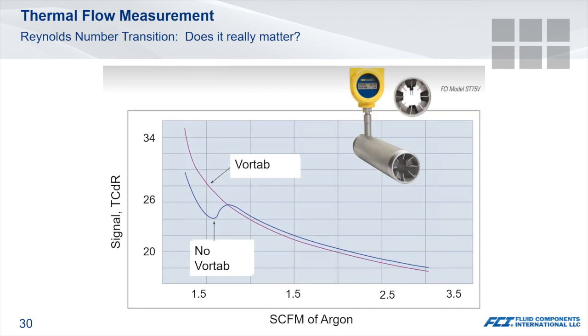This next illustration helps visualize how transitional flow can impact thermal measurements. The blue curve shows the signal from a thermal sensor when flow passes through the transitional zone. The result is a noticeable fishhook in the output. When unaccounted for, linearization of the analog output can introduce an error of plus or minus 10%. Ideally, we want our sensor output to be smooth like the curve in purple.